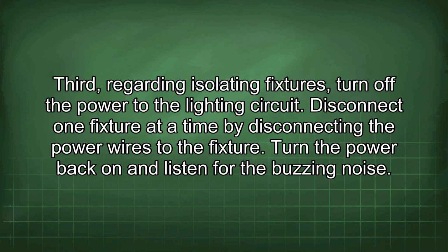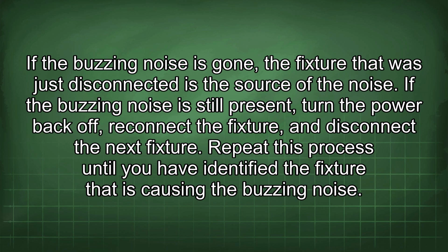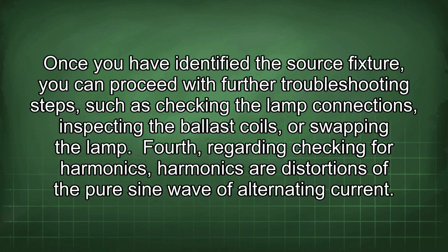Third, regarding isolating fixtures, turn off the power to the lighting circuit. Disconnect one fixture at a time by disconnecting the power wires to the fixture. Turn the power back on and listen for the buzzing noise. If the buzzing noise is gone, the fixture that was just disconnected is the source of the noise. If the buzzing noise is still present, turn the power back off, reconnect the fixture, and disconnect the next fixture. Repeat this process until you have identified the fixture that is causing the buzzing noise. Once you have identified the source fixture, you can proceed with further troubleshooting steps such as checking the lamp connections, inspecting the ballast coils, or swapping the lamp.